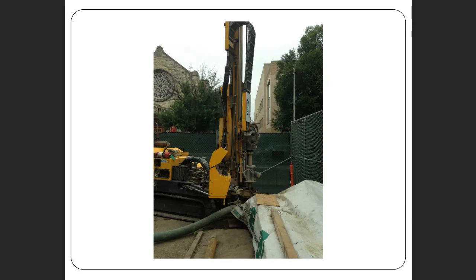Yes, this work was permitted. It was subject to a building permit, as any major construction project would be. We also did a test well, which is typical for a large geothermal installation. A few years earlier we drilled another well on the property and measured the characteristics of the soil, how well it would allow us to transfer heat. The designers used the data from that test well to design this system, so we had a good idea how much heating and cooling capacity we could get from each borehole.